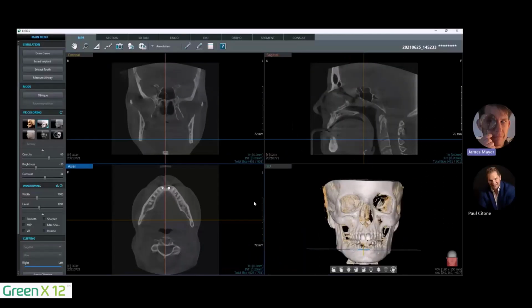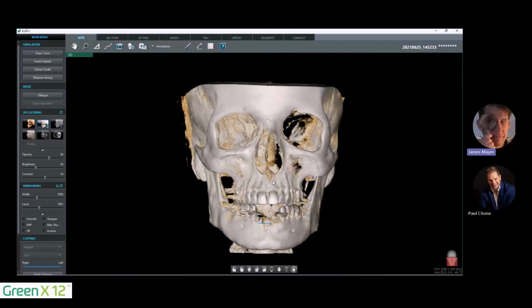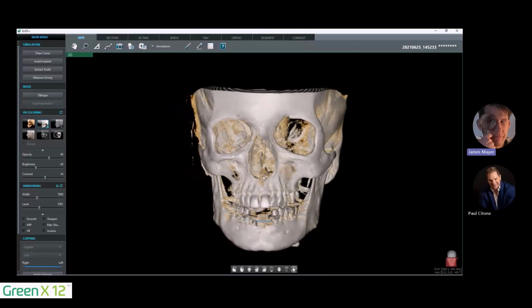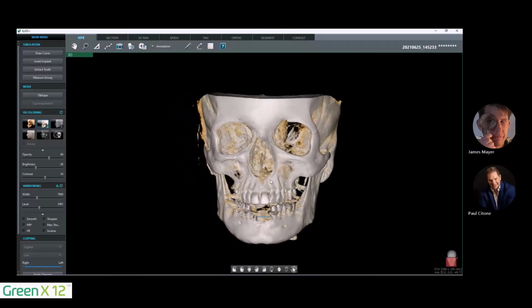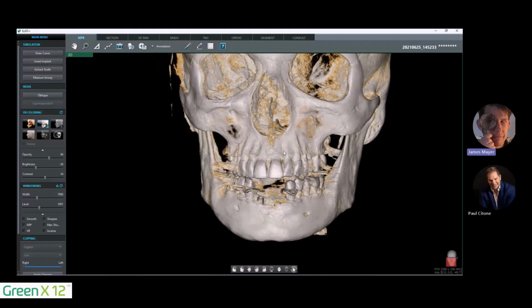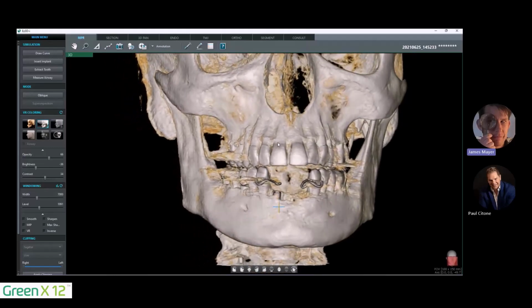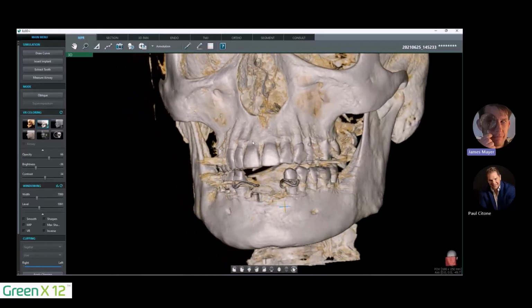So Paul, we just finished up looking at patient movement. Now let's look at a little bit of distortion or artifact you see in scans that's highlighted as scatter in the images. So I'm going to go ahead and enlarge our 3D rendering here. And we can see off of any dense areas, you can see a little bit of scatter or streaking effect in the image.